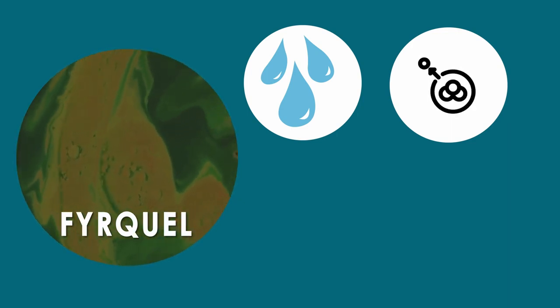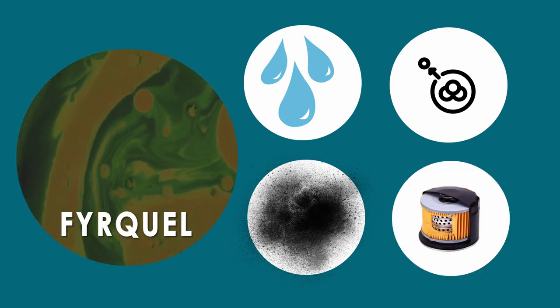Contamination and decomposition products cause a decrease in resistivity, and a low resistivity fluid can give rise to corrosion of valves. Clogging of filters is also a concern — when exposed to extreme temperatures, Fyrquel fluid develops dark particles, which cause silting of valves and accelerate clogging of filters over time.